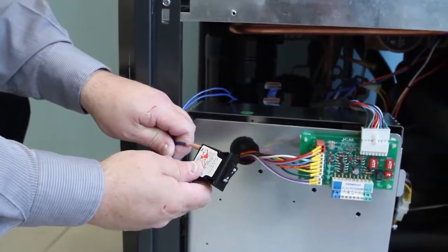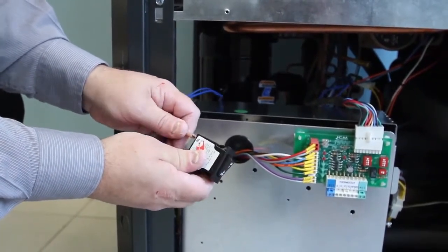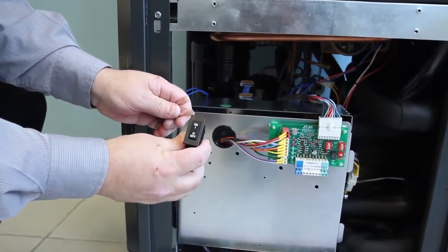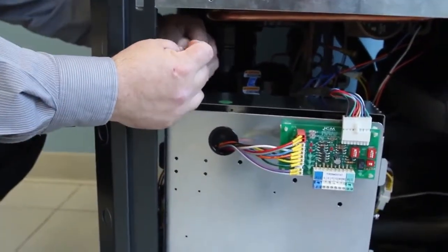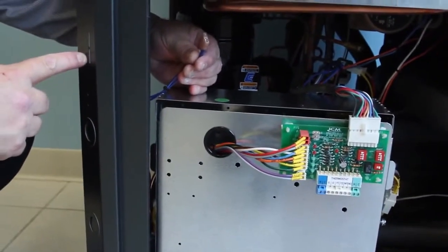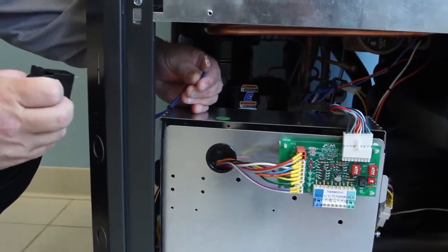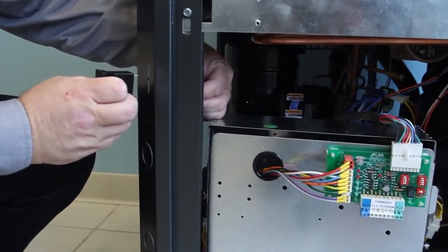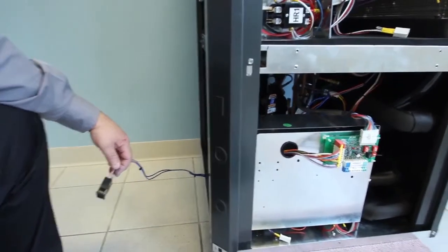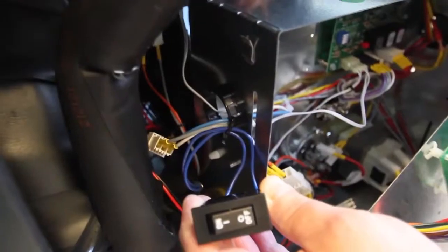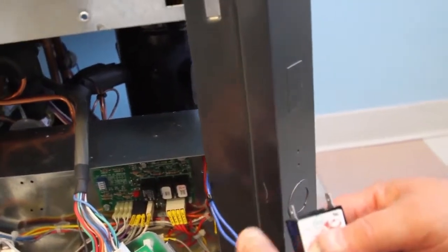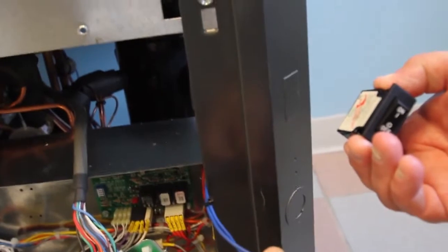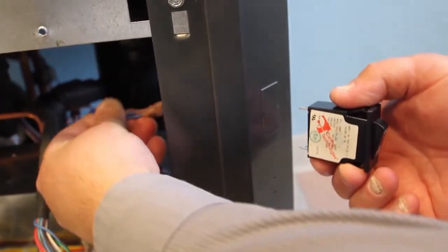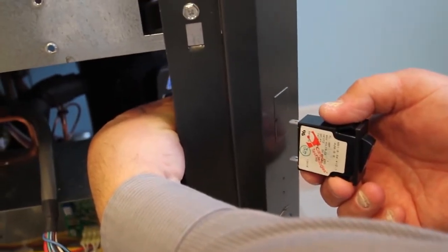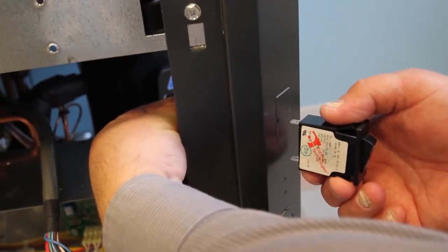The fifth set of instructions is for the HRP switch, and this is only needed on the units with factory installed hot water heat recovery packages as we have on this model. The disconnect switch is shipped loose inside the unit E-box, and it can be connected to either the front right corner post or the back right corner post when converting it to right-hand return. From the inside of the unit, remove the two wires connected to the HRP pump disconnect switch. Identify a rectangular knockout and remove it on the right front corner panel in the right-hand position. Install the HRP switch into the knockout and reconnect the switch wires.